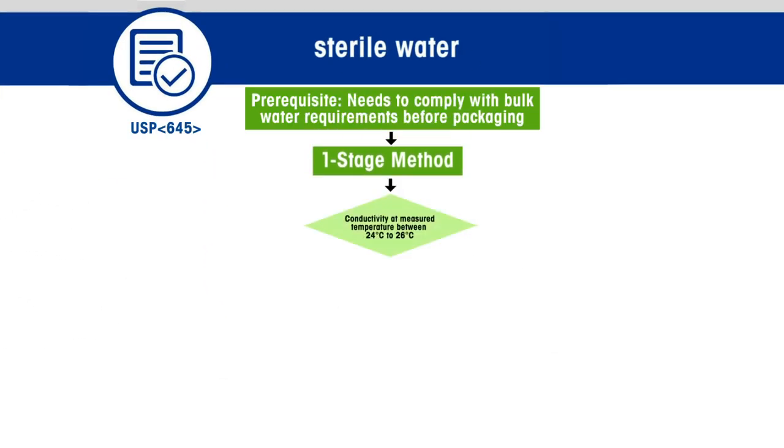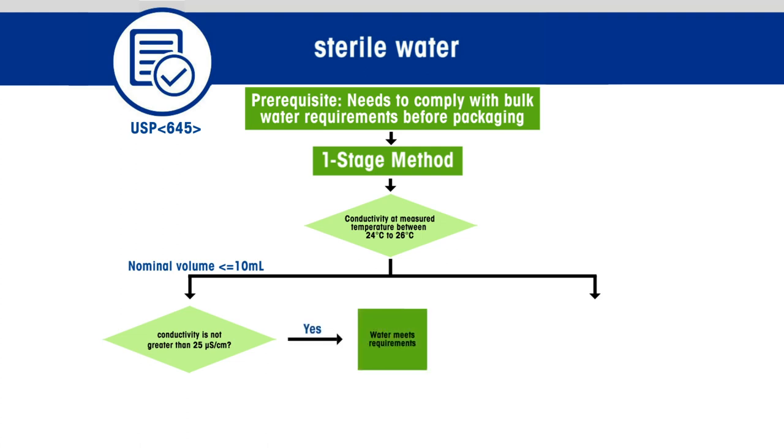Maintain the sample temperature between 24 and 26 degrees Celsius while stirring to obtain carbon dioxide equilibrium. Then measure the conductivity. The passing criteria depends upon the nominal sample volume. You may need to collect the water sample from multiple containers to reach enough volume to measure the conductivity. If the nominal sample volume is less than or equal to 10 milliliters, and if the conductivity is not greater than 25 microsiemens per centimeter, the water meets the requirements.